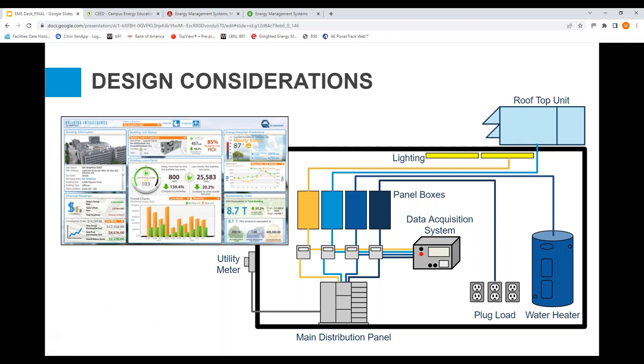Two other things really quickly. The other thing that I see a lot of is that we can now get so much information from pieces of equipment. For example, on an air handler, there's a VFD, a variable speed drive, so that we can speed up and speed down the fan. Let's say you have 10 of those on your project. Each one of those VFDs could have 100 points on them, but the ones you would probably only use are kW or kWh. The rest of the points you're probably not going to use. Maybe there's a few, but I would say a handful versus 100.